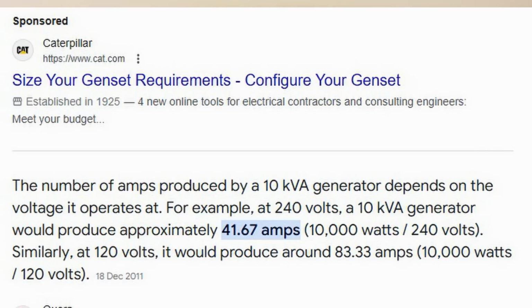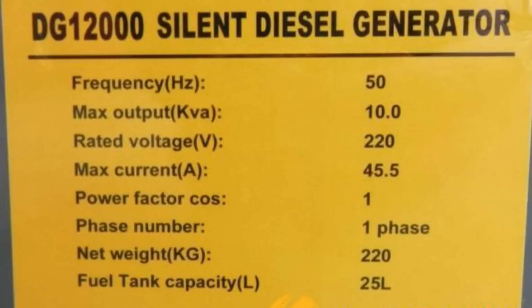So imagine you're going to buy a 10 kVA single phase generator. The equipment sticker, or the nameplate rating on the piece of equipment - I'll try and find a picture for you - you should see something around 40 to 45 amps for a 10 kVA single phase generator.